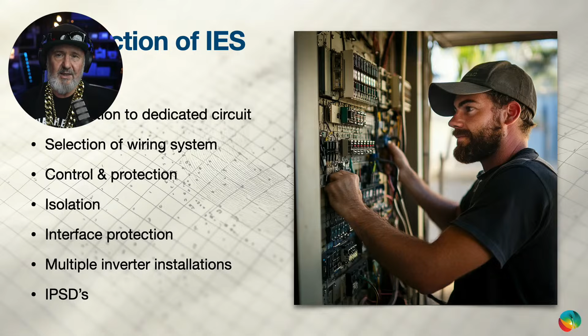Okay, connector requirements. So get my face out of the way there for a second. The IES shall be connected either by fixed wiring or by a connector coupling arrangement. Now, what does that mean? Well, most of your domestic inverters these days often have a shrouded male coupler that you connect, and it requires a tool to remove. And so that's an installation coupler. It's not a 3-pin plug, right? And the requirement is that those connectors are of type B. Now, type B meaning that they require a tool to disconnect. Now, we did have, speaking of recalls, a recall from, I think it was Growatt actually, because you could remove the connector without a tool, and I think you could even expose the terminals without a tool. So that was a little bit of an oops. So yeah, type B connectors are required.